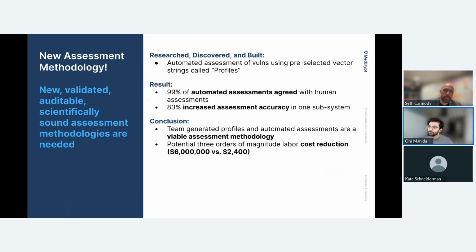Yeah, what we've seen be successful at device manufacturers of various sizes is doing it as often as you can. We know post-market vulnerabilities need to be regularly monitored. Seth, that slide you had on the number of vulnerabilities that come out annually, and that number only going up, means that the software you're shipping today, once it's out in the field, has a very high probability of having vulnerabilities the longer it's in the field. So making sure you systematically, on a regular basis, monitor and check for vulnerabilities as often as you can is really critical.